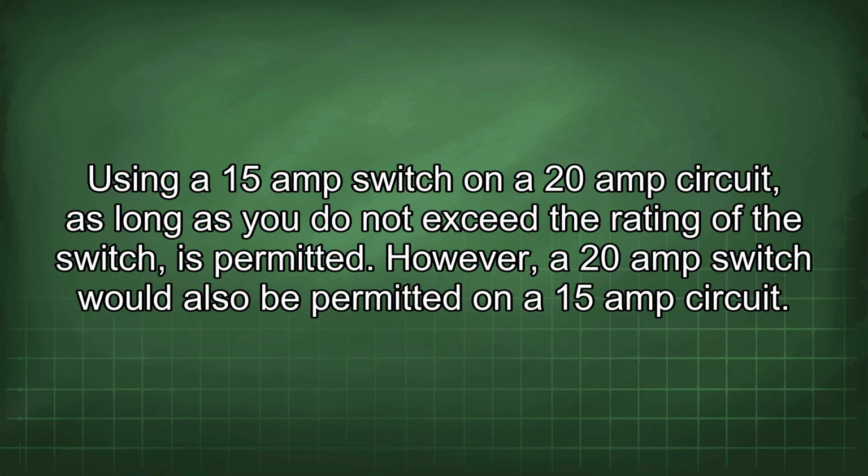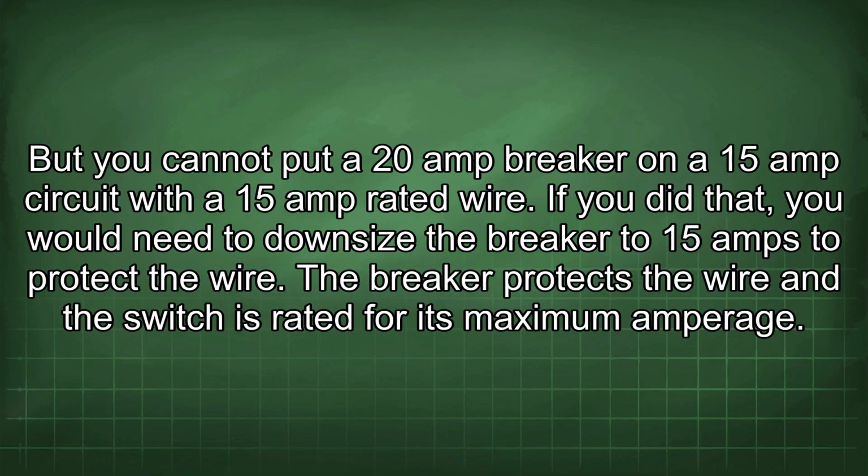Using a 15 amp switch on a 20 amp circuit, as long as you do not exceed the rating of the switch, is permitted. However, a 20 amp switch would also be permitted on a 15 amp circuit. But you cannot put a 20 amp breaker on a 15 amp circuit with a 15 amp rated wire.